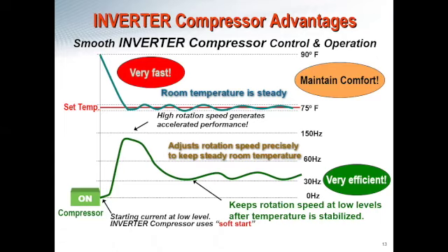So once you get to your set point of 75 degrees, as we see here, you're really just scaling back and only giving the amount of energy to that compressor that it needs to maintain that set point. You're not letting the set point fall and chasing back up, or letting the set point rise above and chasing back down. You're purely maintaining what you get, and it's a lot easier on the compressor, and it actually allows the compressor to last significantly longer than your traditional compressor.